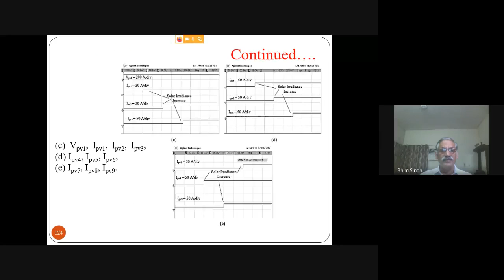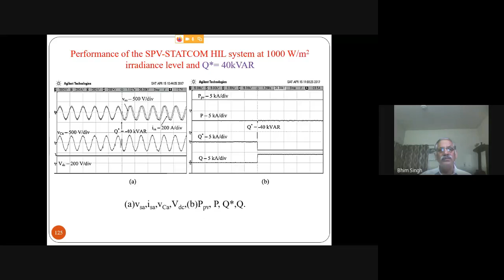But we didn't extend multi-level for this power quality aspect. It should not have harmonics of its own, but the filter voltage and all that we handle. We are able to inject reactive power, both leading and lagging, in this feature, because we expect multi-level converters to be used at large ratings, where reactive power may be required but harmonics may not be a major concern at large power and voltage ratings.